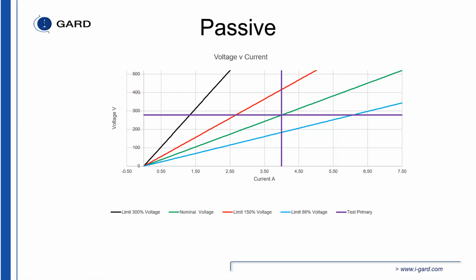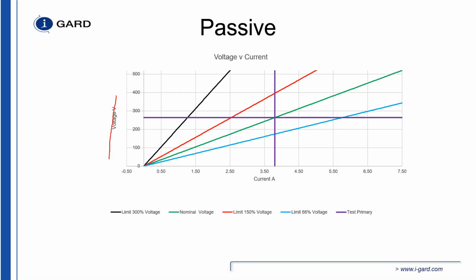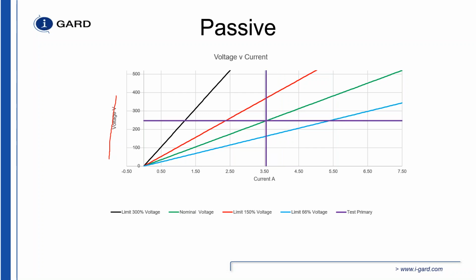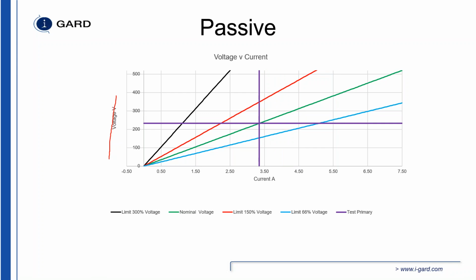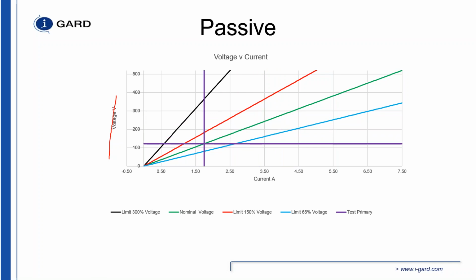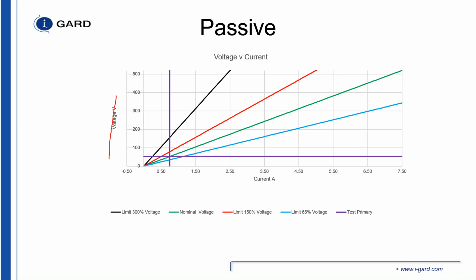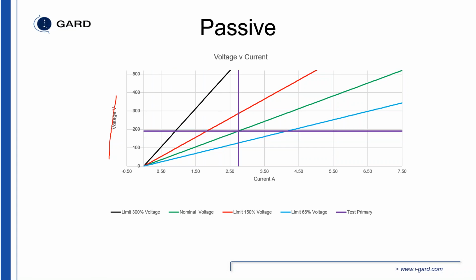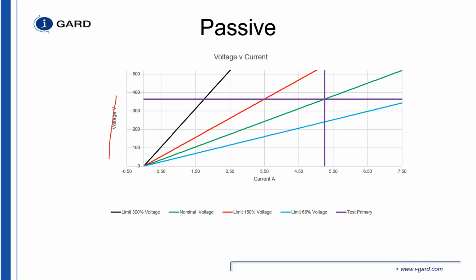To give you an example, we normalize the voltage across the resistor through an NGRS, and we measure this voltage here. We also measure the current with our zero sequence CT. As long as everything continues to operate, when you have a ground fault on your system, the voltage and the current increase or decrease at the same rate, and they follow that green line.